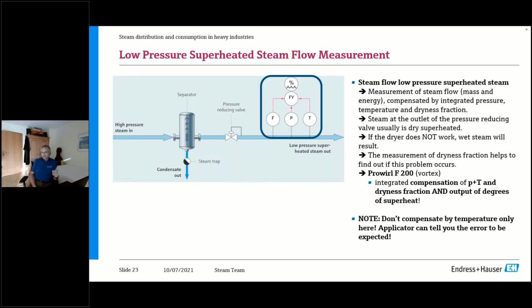And in addition to that, please always also compensate by the dryness fraction. Why do I say so? I just mentioned it's superheated steam. Well, in theory, yes, and not always, because don't forget you have a steam trap sitting here. This is problem number 1. Steam traps are mechanical devices. So if you don't properly maintain them, you will have cases where they fail. And what happens then? Your separator is going to drown, and you get wet steam in, and you also get wet steam out.